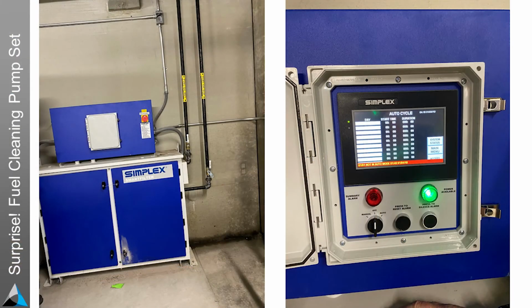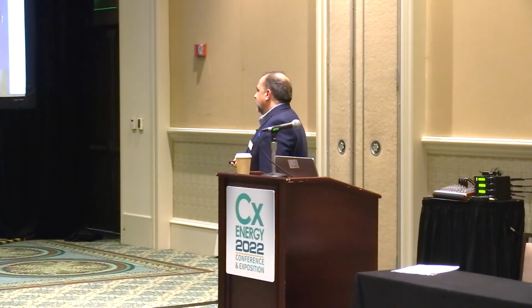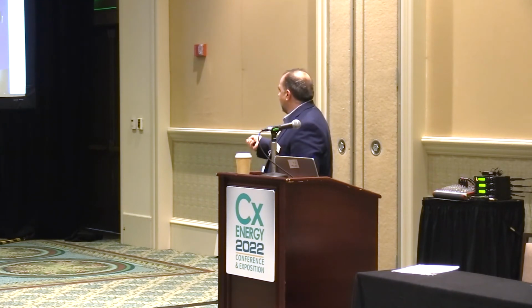What we weren't expecting, and nobody specified, and I didn't see in the submittals, was a separate fuel cleaning system. The fuel can't just sit stagnant in a tank and be expected to work. So somehow they got this nice system where it pumps the fuel out of the main tank through the fuel polisher in this cabinet, then pumps it back to the tank. It does that on a regular schedule, if you could see, there's like a little calendar, a programmable schedule.